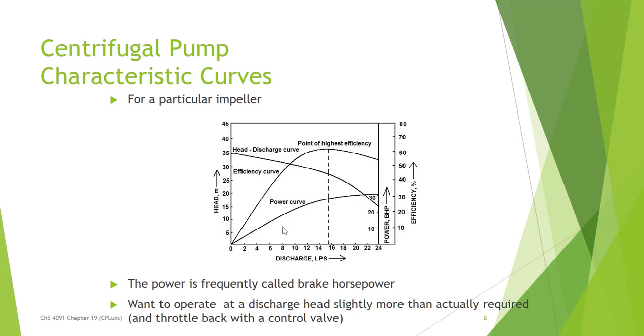A centrifugal pump is one that you will have looked at characteristic curves — or pump curves — for in a previous course. Generally we have a flow rate versus a pressure head plot, and we look at both the head on the discharge side and how much power we need, trying to match this to where we find maximum efficiency. That's usually somewhere in the middle of the set of curves — not at either end. The power they refer to is called brake horsepower. You'll want to operate at a discharge head a little bit more than what you really need, and then use a control valve to throttle that back, giving you room for operability.